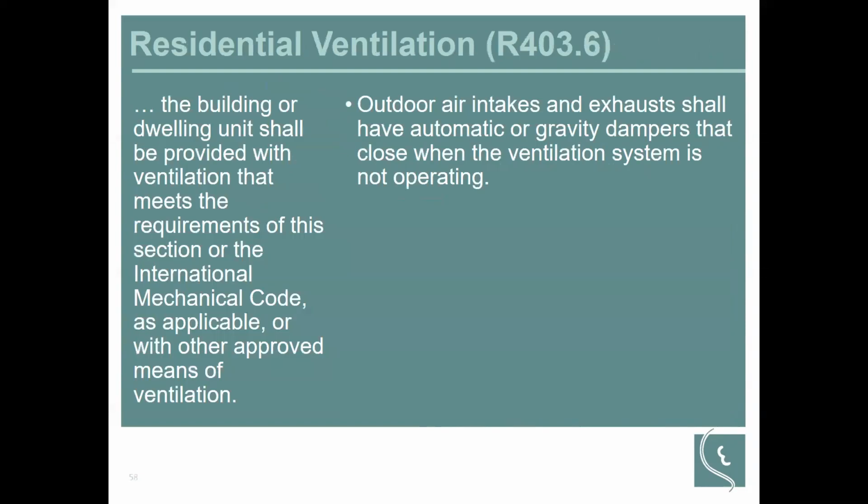Residential ventilation, again, making sure that we provide ventilation. And as Robert noted, there are a couple of different ways this can be done, whether it's supply only, exhaust only, or balanced. Supply only and exhaust only can cause moisture issues, particularly as you end up with air leaking through your assemblies, potentially causing some indoor air quality issues through that air leakage. Balanced systems make energy recovery and heat recovery much easier to do in a single unit to provide both the supply, the exhaust, and heat recovery. But we do require ventilation per the mechanical code or the other requirements within the code.